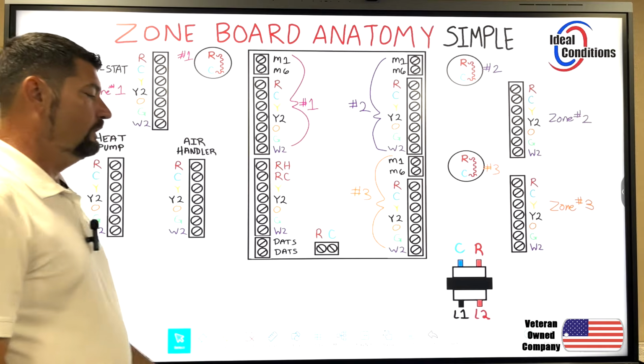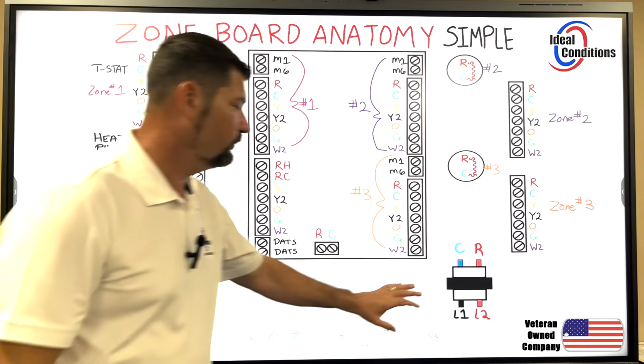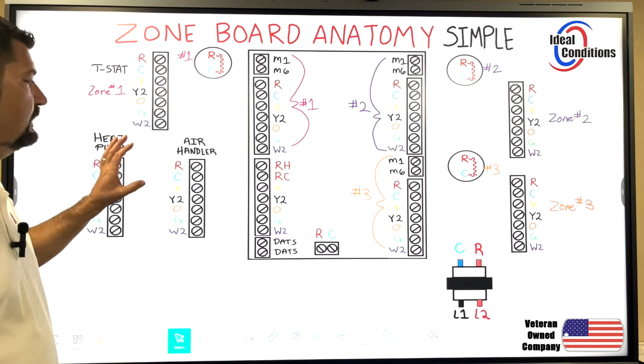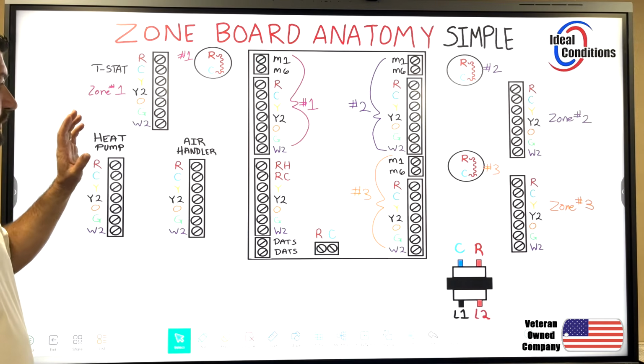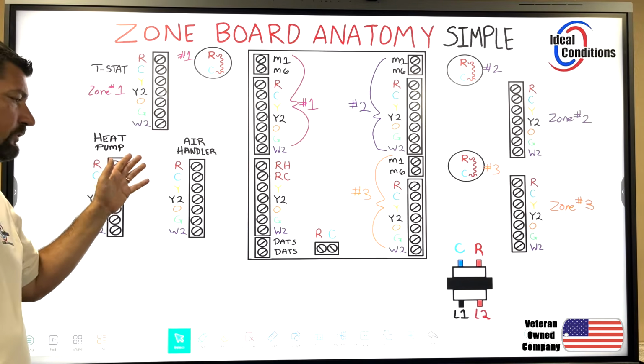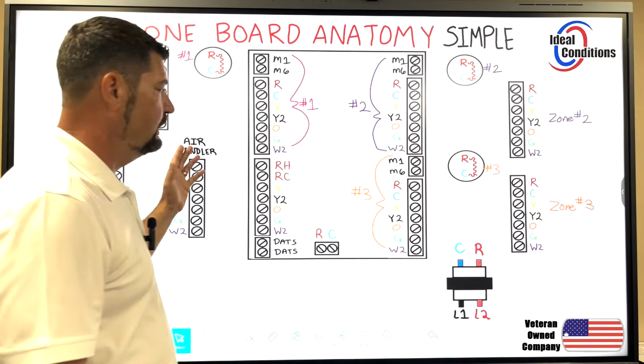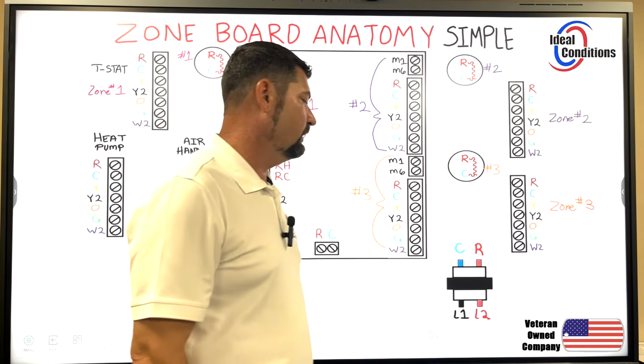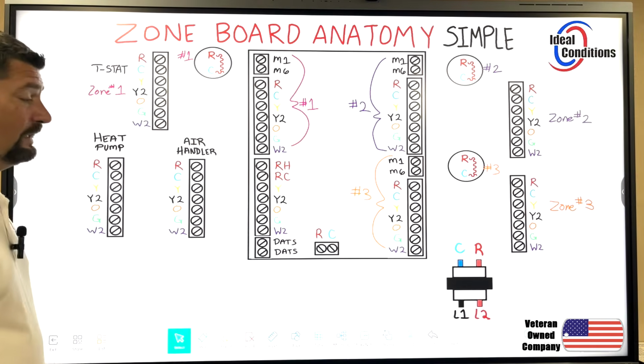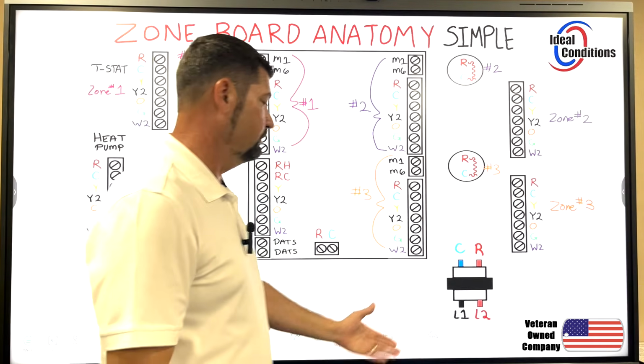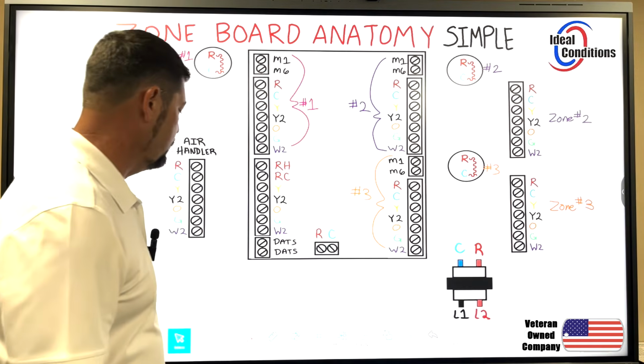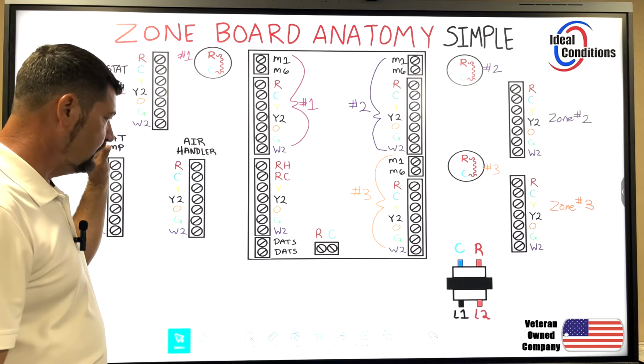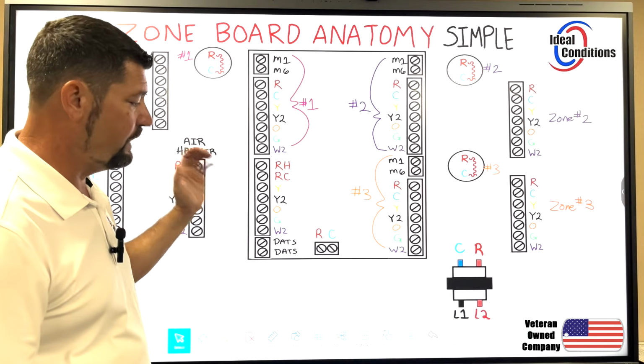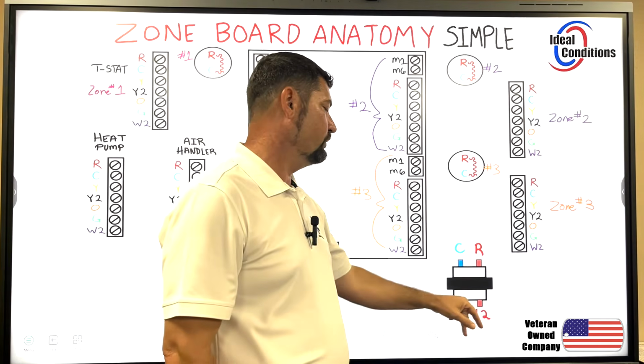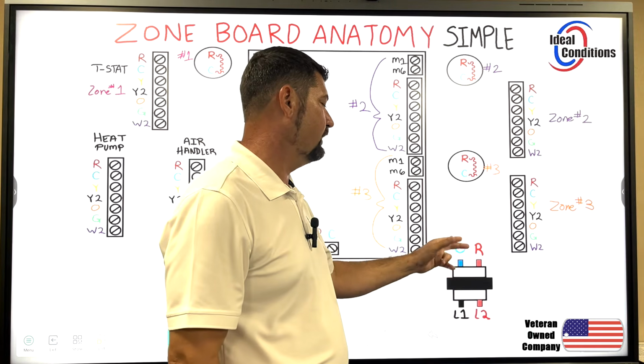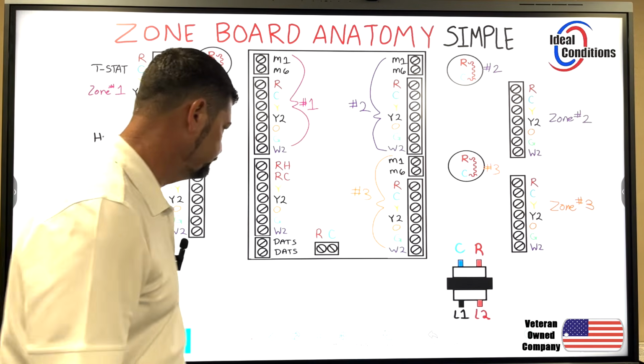We have L1, L2. Obviously, this transformer will be found inside the air handler. So if I had a primary transformer that the manufacturer put there that's a 40 VA, and I'm putting in a zone system, whether I buy a kit or don't buy a kit, I would take a 40 VA transformer and I would add that. Of course, I would have to power it with L1 and L2, so I have 230 volts, so I can step power down to get my 24 volts.